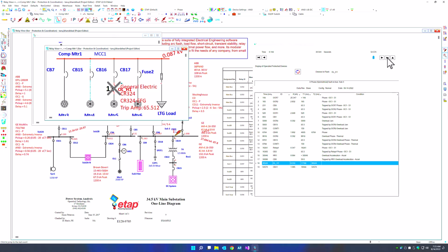You can essentially pick another device. In this case, it happens to be circuit breaker 8, which is tripped by overcurrent relay number 7. And the program will flash and indicate and let you know in the sequence, this is the first device that essentially tripped in the network. You can essentially move and navigate through the entire sequence one by one.